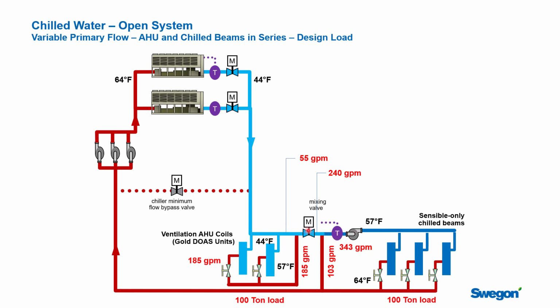This is just a balanced flow calculation. And when you do it, you're going to work out you need 103 GPM of 64 degree water to mix with 240 GPM of water that's slightly less than 57, and that is going to deliver 343 GPM of 57 degree water to the space. This system is going to work fine. There are no issues, and there are no issues as long as this flow in here is always greater than this flow over here, which is actually likely what's going to happen in your building.